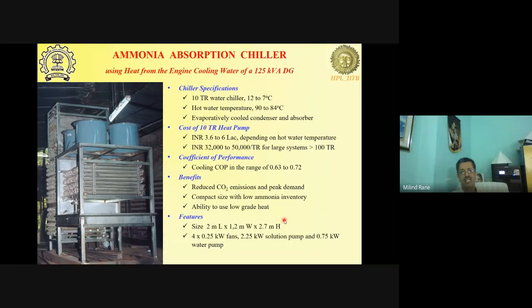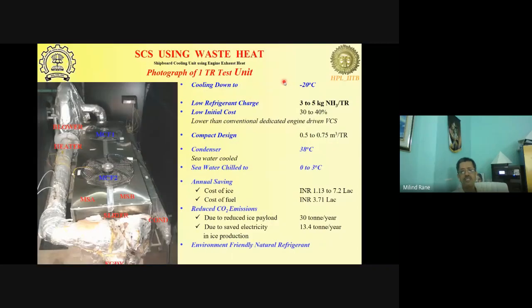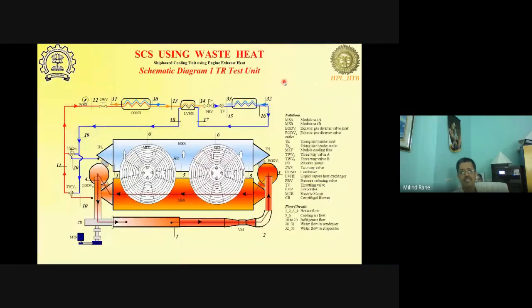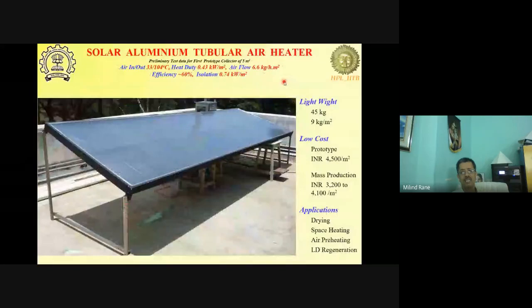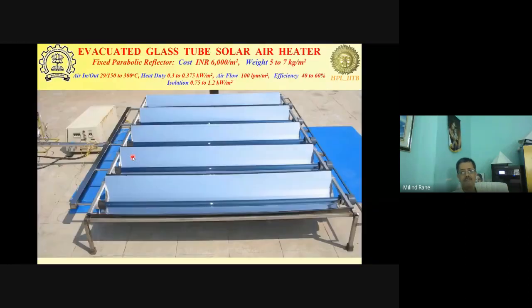Then our radiator hot water fired absorption refrigeration system, 10 ton of cooling possible with a 125 kVA DG set. This we have already discussed, the shipboard chilling unit. Air heaters. Now here you can see the temperature going up to 104 in a single pass. Air enters here from ambient at about 33 in this example and comes out at 104 here.